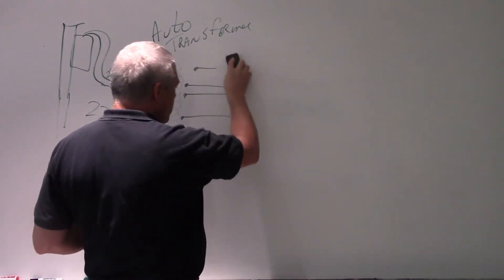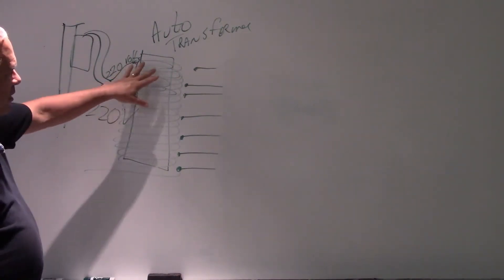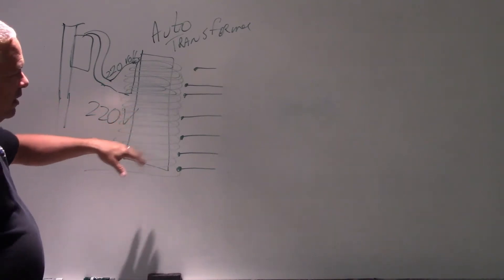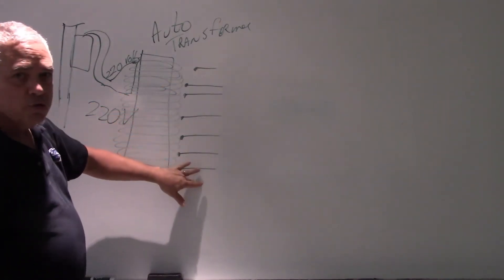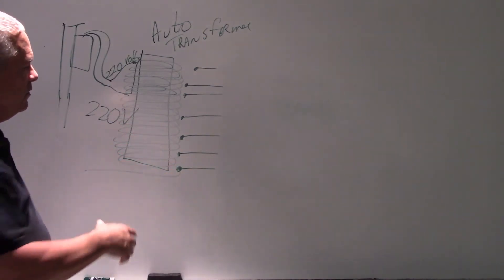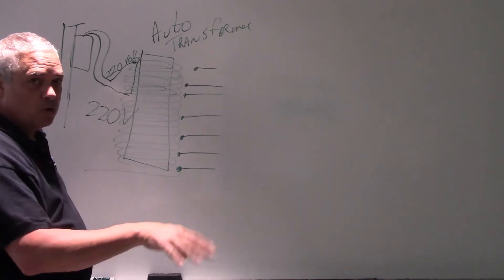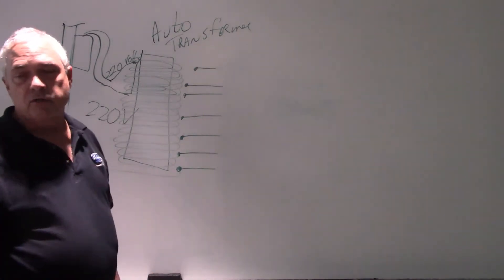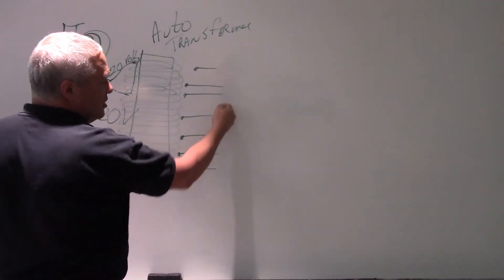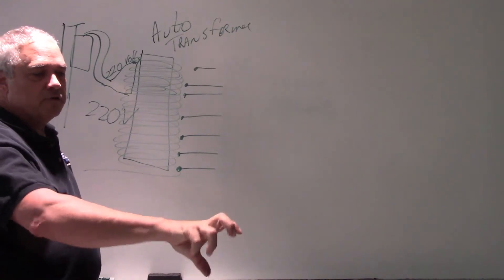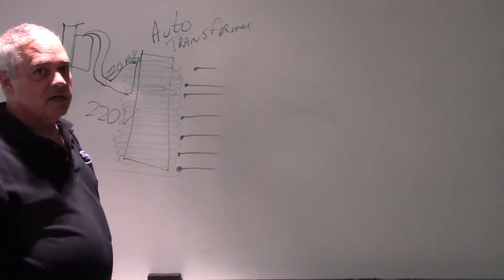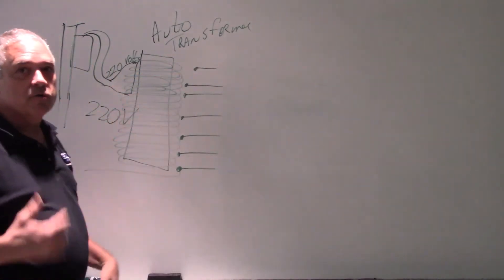So we've got electricity coming in, and we've run it through the auto transformer, selecting how much of it we're going to use. This is basically the function of your kVp selection whenever you're selecting kilovoltage on the control panel. You might hear the box in the corner clicking — those are relays selecting which taps to use. As you change from 60 to 70 to 90 kVp, you'll hear those relays clicking, adjusting the auto transformer coils.